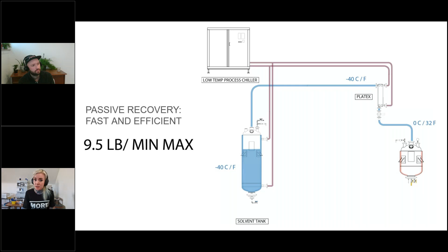And it creates an opportunity for you to break that pump because those pumps do not like to pull vacuum. When you run them at vacuum for a very long time, you can dry them out. That's where people are cracking those diaphragm seals. If you're rebuilding your recovery pump more than once a year, you better be processing millions of pounds. And even then, if you switch to passive, there's nothing to rebuild. You might replace hoses on a manufacturer recommendation, but the worst case scenario with passive is nothing happens.